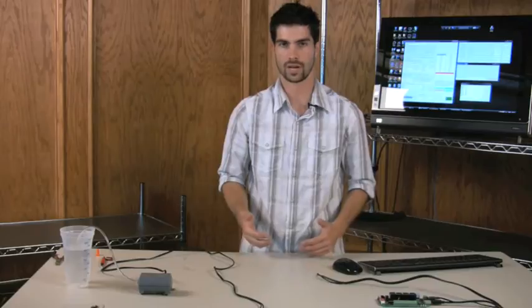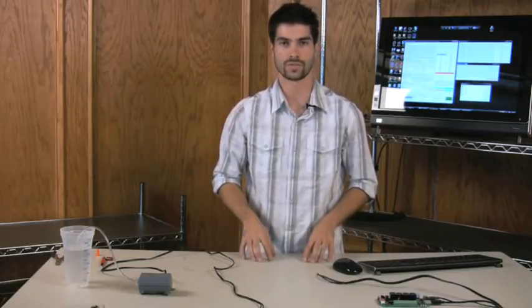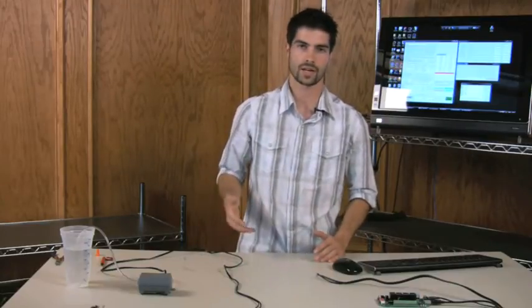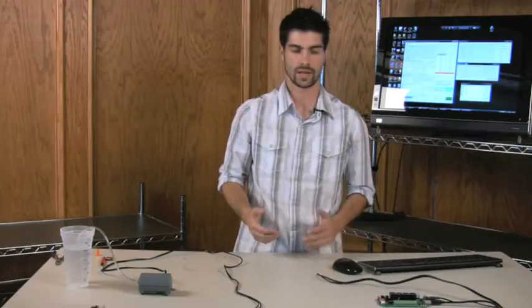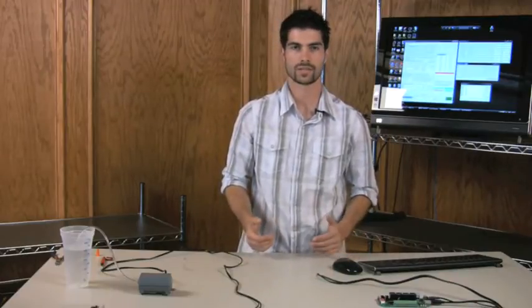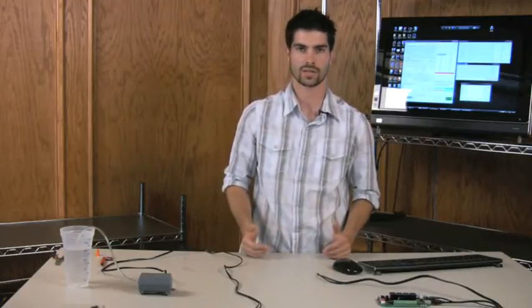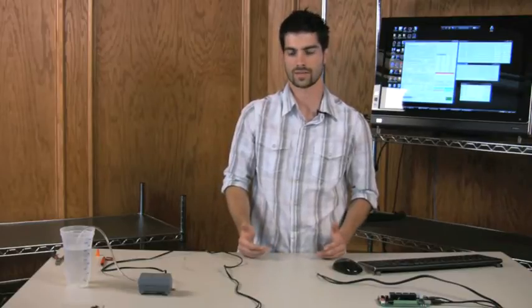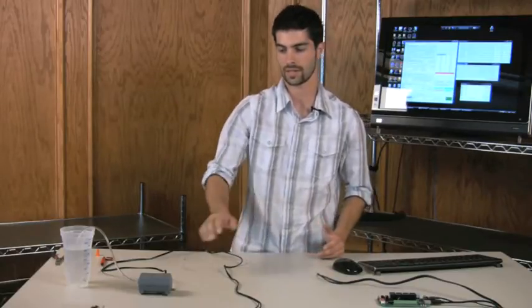One of the main problems a lot of our customers have is induction. That's why I'm doing this first video on it. Induction is voltage spikes that we call EMI that come back from devices that are attached to our controllers. These voltage spikes can cripple communications from the controller to the computer. It causes these problems and they're just really big headaches. It's really frustrating for customers because the device will work one time, maybe three times, and then just quit working. You don't know why. A lot of times, that's induction if you have something like this attached to it.